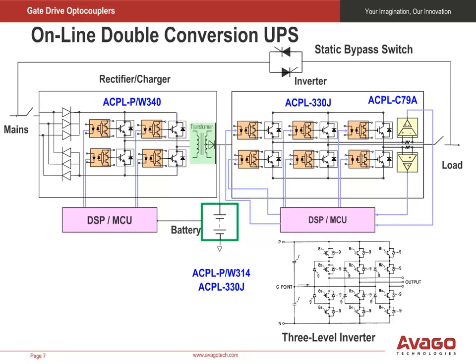Another important application is the online double-conversion UPS. Isolated gate drivers are used in the rectifier and charger, as well as the three-phase inverter. The AC mains input is rectified to obtain a DC bus voltage that supplies power to the three-phase inverter. A single-phase inverter charger charges the battery bank; it is full-bridge, and the four channels of isolated gate drivers are designed with the ACPL-P340 or ACPL-W340. Instead of a conventional two-level three-phase inverter, more three-level three-phase inverters are being designed, using 12 isolated gate drivers—six ACPL-330J drivers and six ACPL-P314 or ACPL-W314 devices. Isolated phase current and bus voltage sensors are also needed.